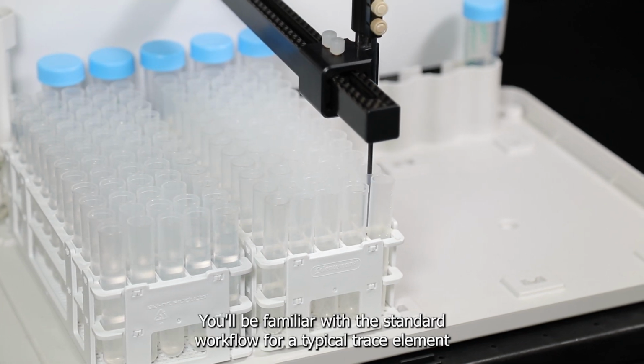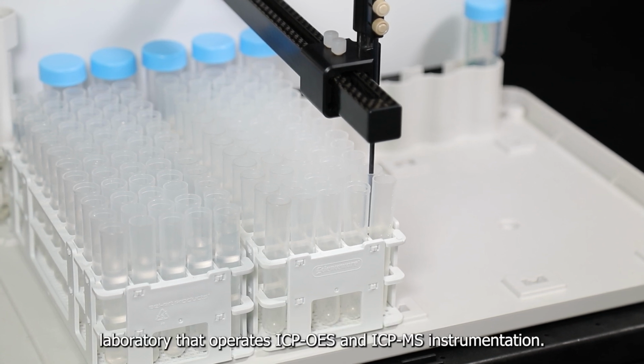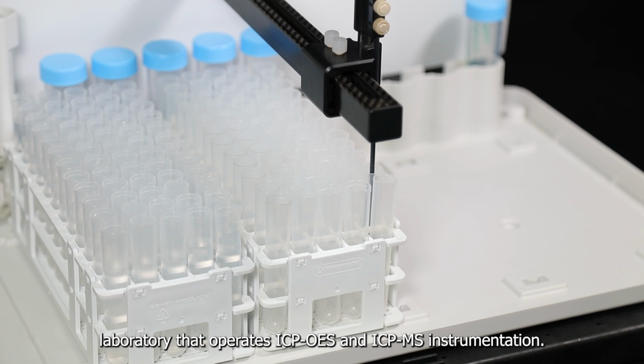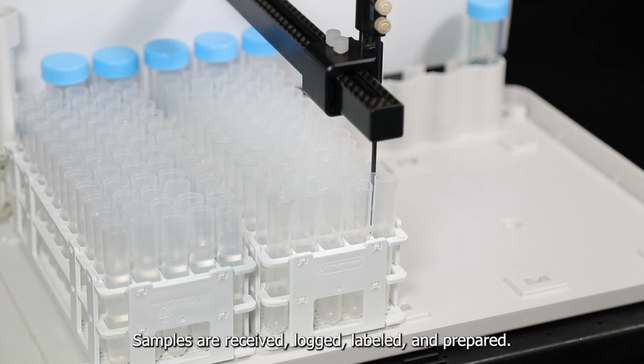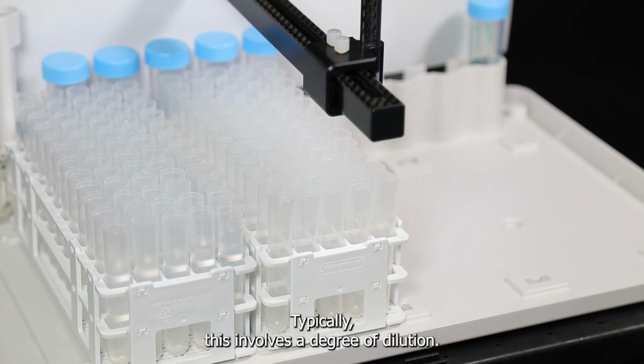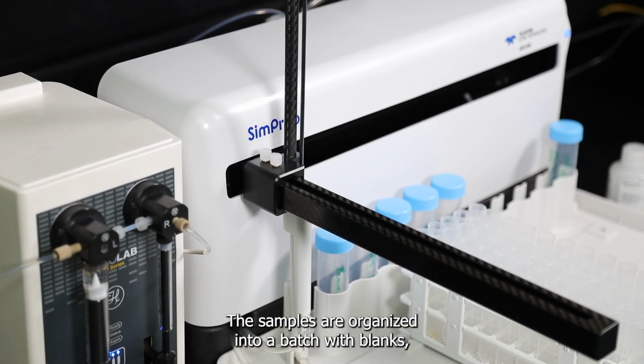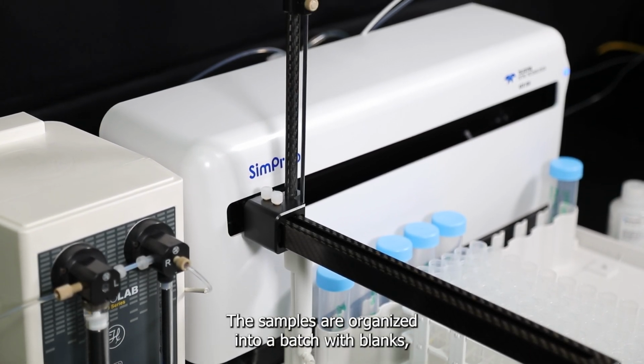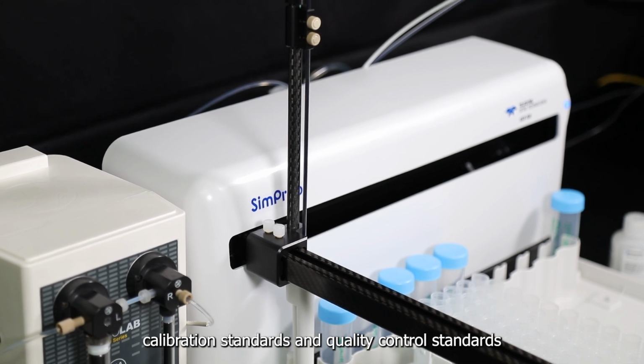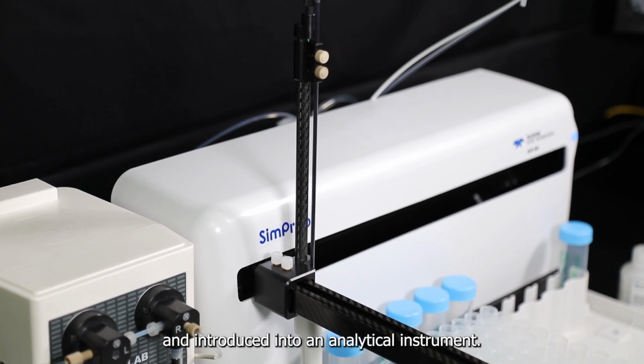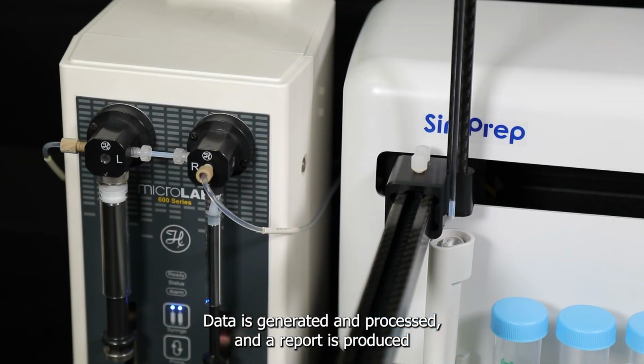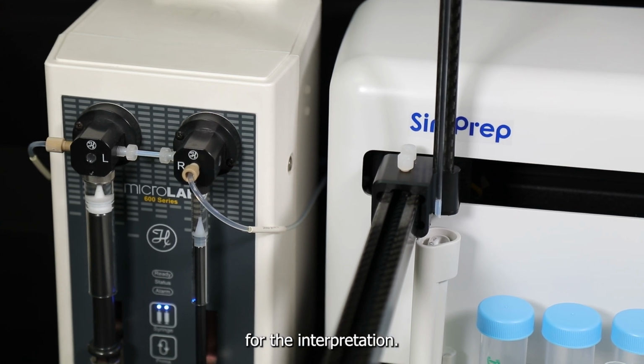You'll be familiar with the standard workflow for a typical trace element laboratory that operates ICP-OES and ICP-MS instrumentation. Samples are received, logged, labeled, and prepared. Typically, this involves a degree of dilution. The samples are organized into a batch with blanks, calibration standards, and quality control standards and introduced into an analytical instrument. Data is generated and processed, and a report is produced for interpretation.